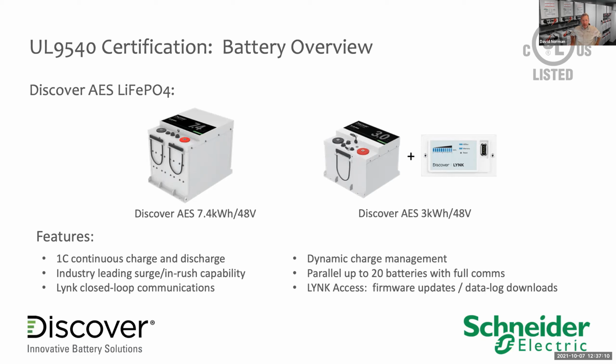Common features between these batteries, they're all 1C continuous charge and discharge capable, meaning they're designed for high currents that would be required in off-grid or extended backup applications. In terms of inrush handling and surge capability, the big battery surges to 300 amps DC singularly. That all is linearly scalable. So if you add 2 batteries, it's 600 amps, 3 batteries, it's 900 amps.